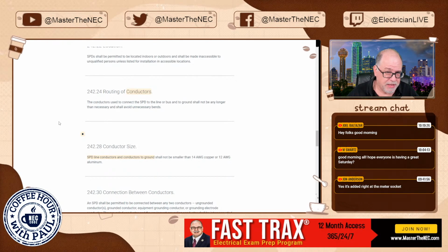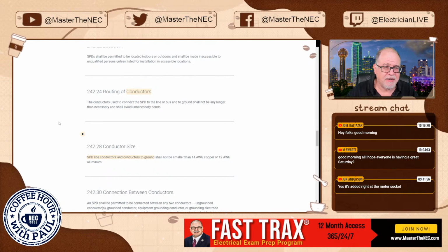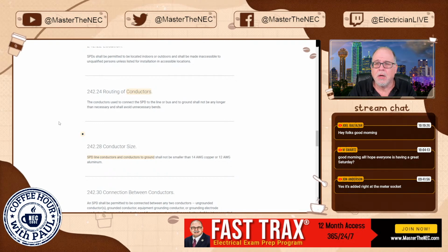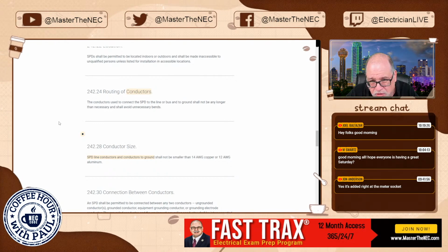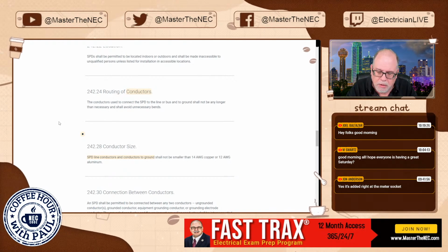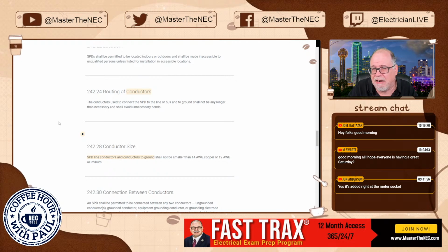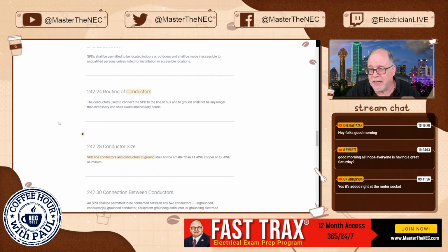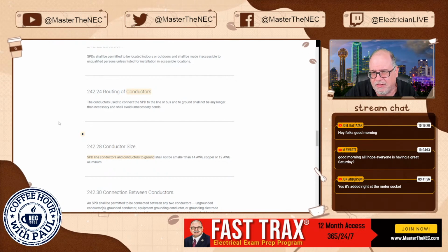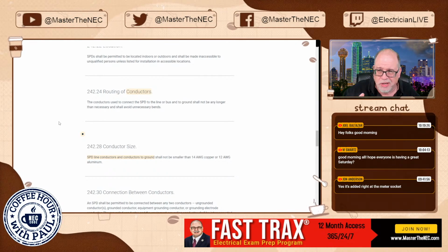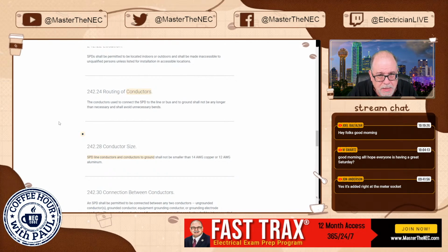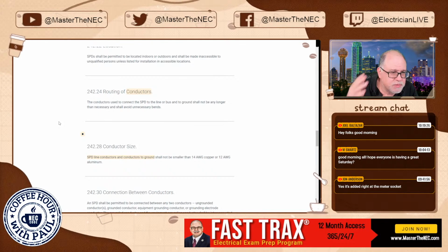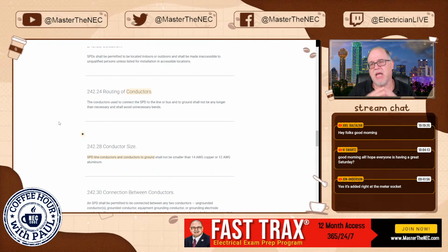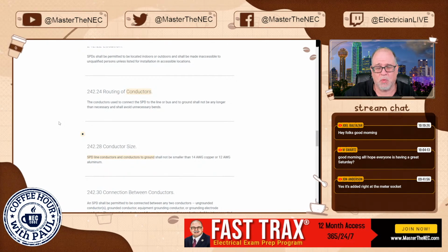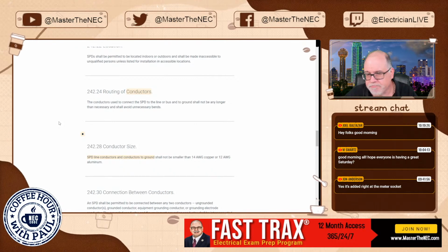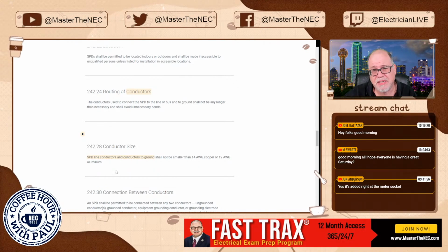Now, why is that important? Because if you do have a surge event, and a lot of these things have warranties, the manufacturers will give you a certain warranty. Well, you've got to read all the instructions, which are 110.3(B), right? They're part of their listing. They might tell you how to route those conductors. And if you do it other than that, and somebody comes out, let's say in a fire investigation, or a representative from the manufacturer comes out because you're going to file a claim, you've got to be careful. Because if there are unnecessary bends, extra wire just looped up, they might blame it on that and say, yeah, you created a choke effect, of course the SPD couldn't work like it's supposed to. So, again, I'm just trying to save you some headache. That's all I'm saying. All right.